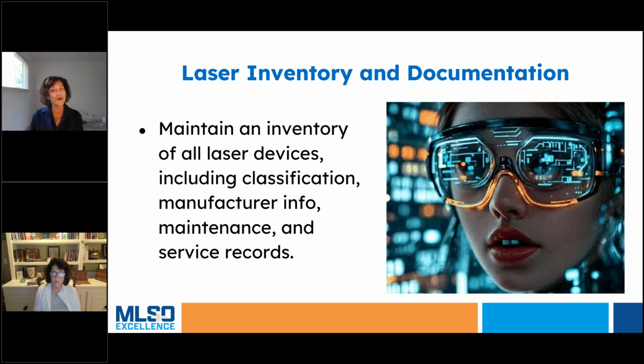Also, and this is regulatory by CMS, you need to follow the manufacturer's designated schedule for PMs, preventive maintenance, and servicing. That means you need the user guide for all of your lasers. If you don't have it, you need to find it, because that user guide, required by the FDA and CDRH, will tell you the schedule of maintenance and preventive servicing needed, and that needs to be recorded and kept on file.